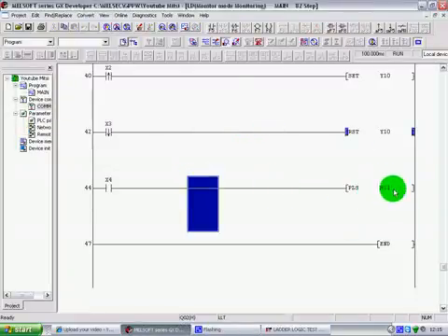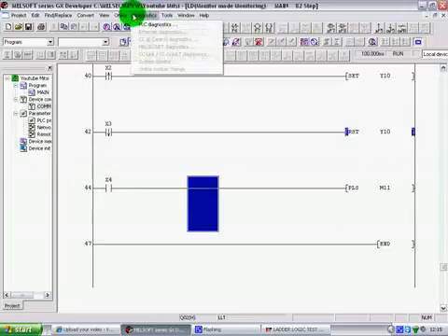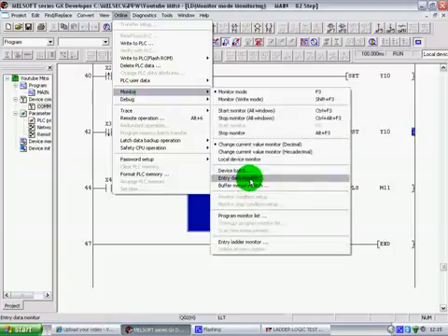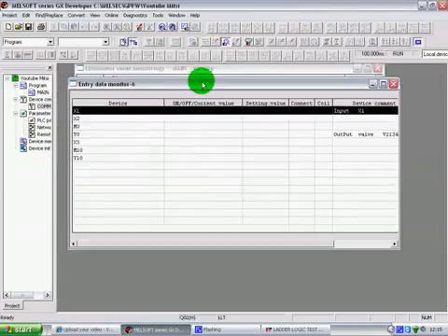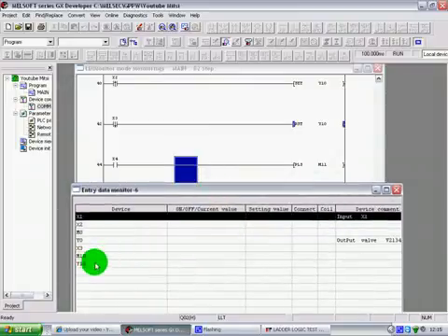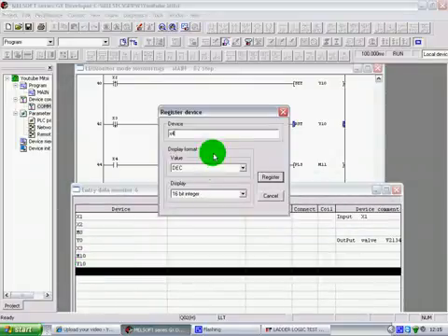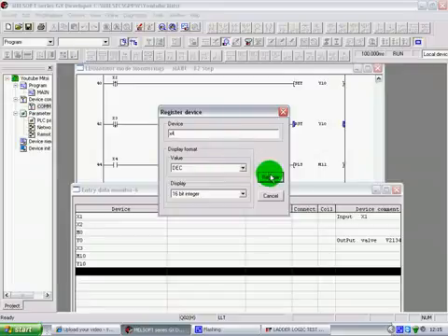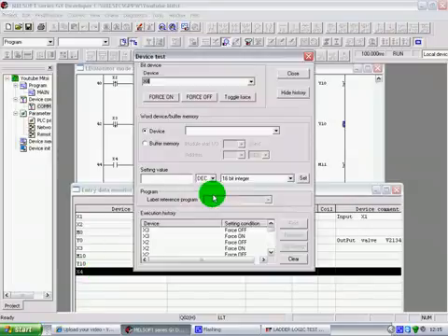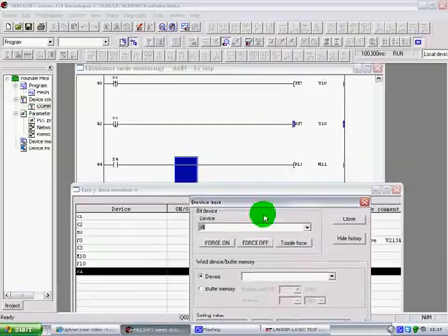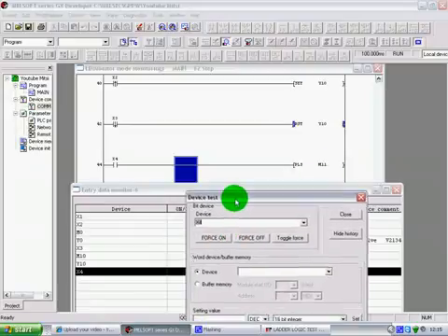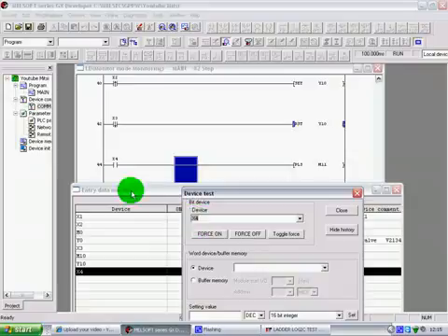Okay, notice that there is no pulse at the moment, it's not high or anything, and X4 is not high. So let's go to our entry data monitor again. Just minimize it so we can hopefully see it. Again, I'm not sure whether the camera will be able to pick it up, but we'll try. I register the X4 device, and if we double click, we now get the device test, and we're going to select X4, which we've got. We'll see this go high, and we'll see if this pulses, if the camera is quick enough to pick it up. So here we go.